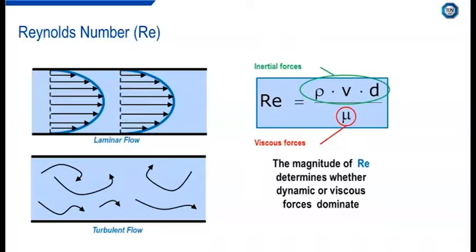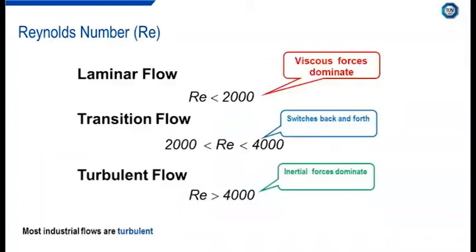And this creates a flow profile or velocity profile, as shown on the screen for laminar flow conditions. At increased velocities and higher Reynolds numbers, the inertial forces dominate and the layers of fluid travelling through the pipe begin to roll past each other, creating a turbulent flow profile. The magnitude of the Reynolds number is used to characterise the flow as laminar or turbulent.